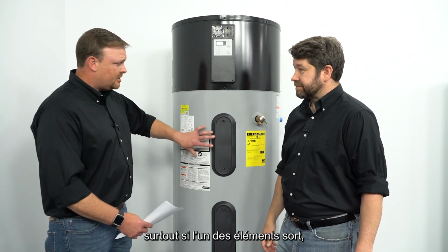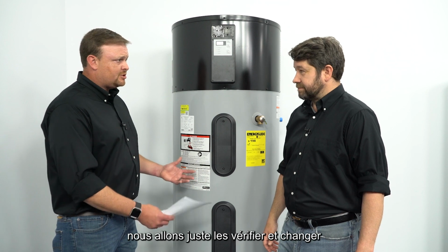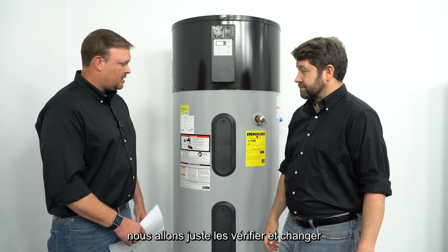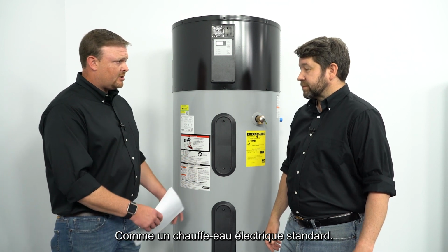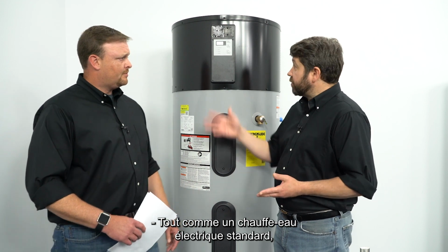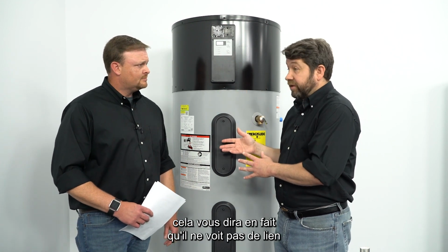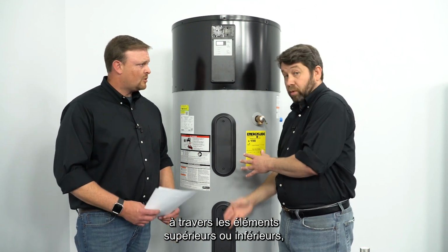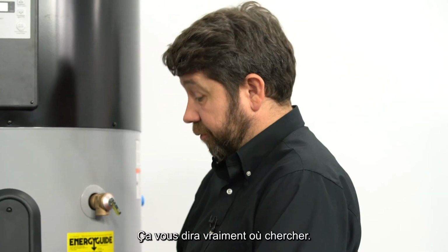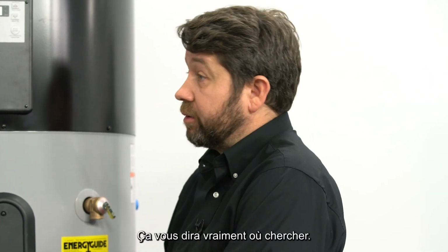And one more thing, with the tank, from here down, it works just like an electric water heater. Especially if one of the elements goes out, we're just going to be checking them and changing them out just like you would a standard electric water heater. Just like a standard electric water heater, this will actually tell you that it doesn't see a connection through either the upper or lower elements. It'll give you that fault, which really tells you exactly where to look.